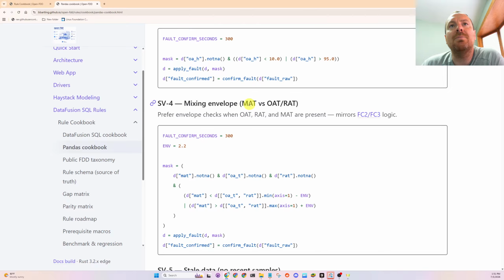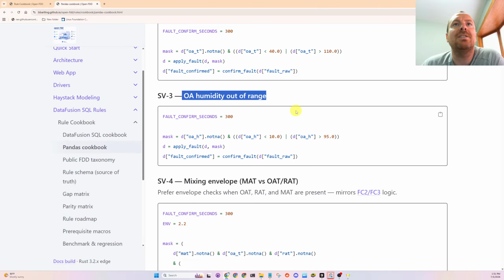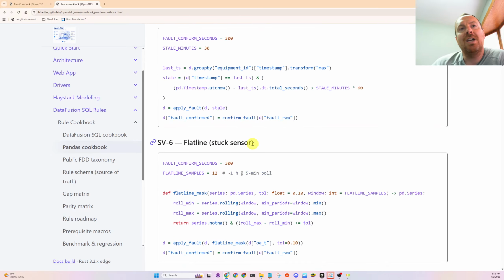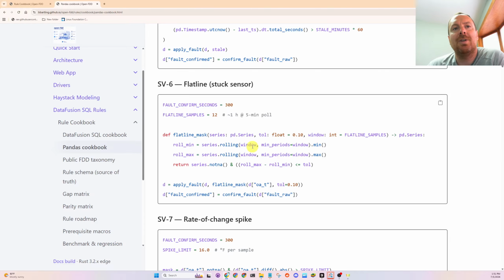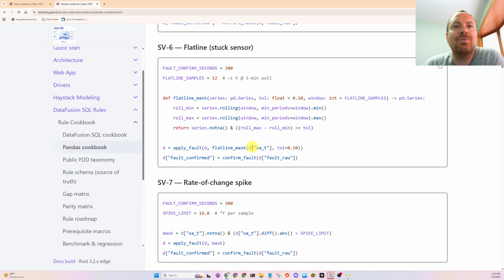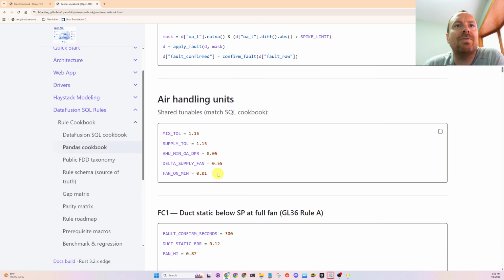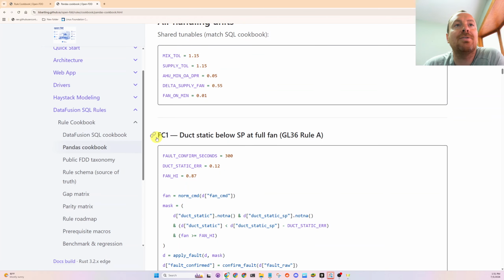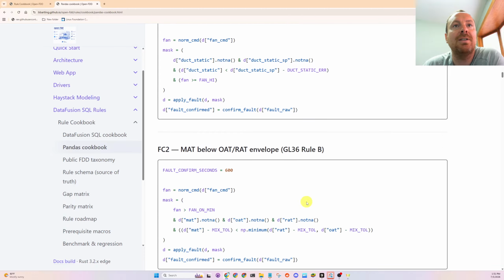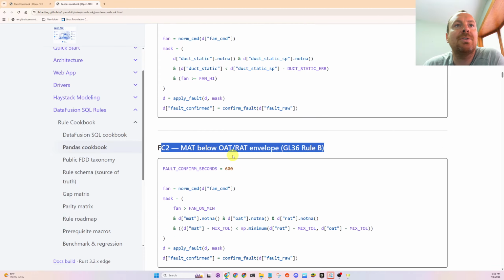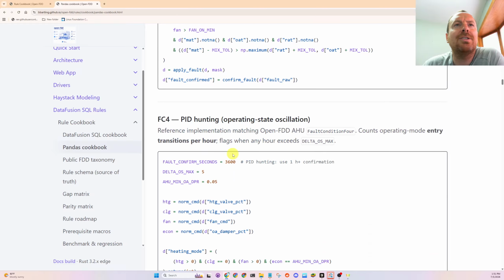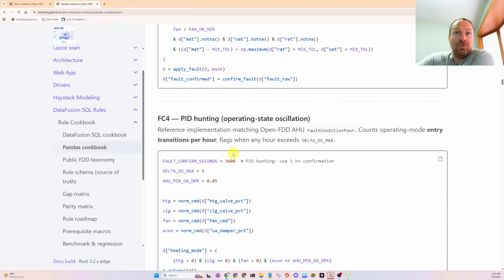Mixing between the mixed air temperature sensor and outside air temp, return temp, humidity sensors out of range—basically just generic fault detection rules. There's one for air handling units, based on ASHRAE Guideline 36: duct static pressure is low when a variable fan system is at full speed. Mixing air temperature sensors. So I'm going to ask ChatGPT to do everything.